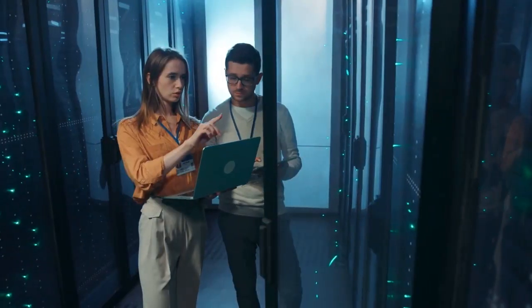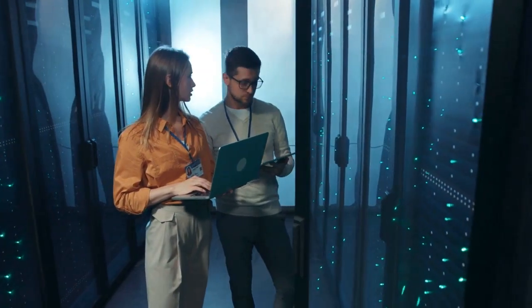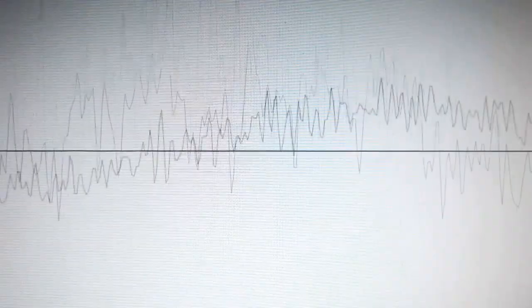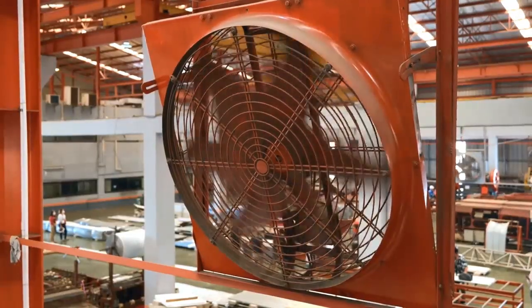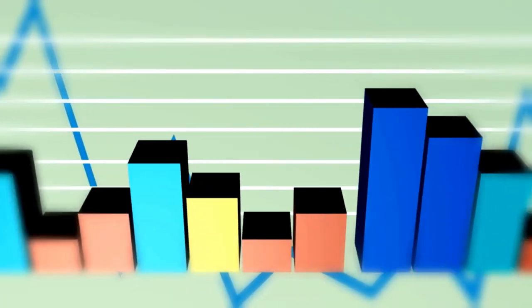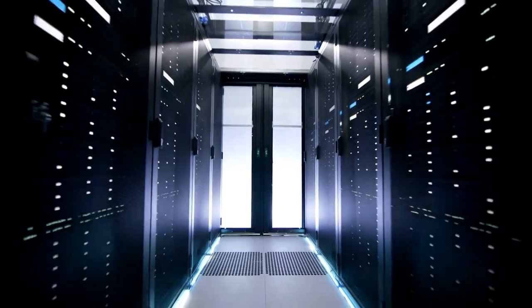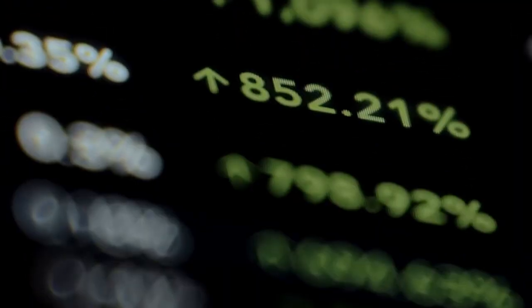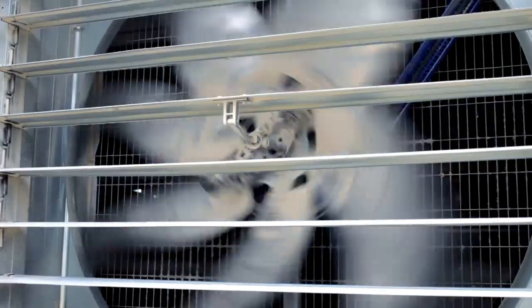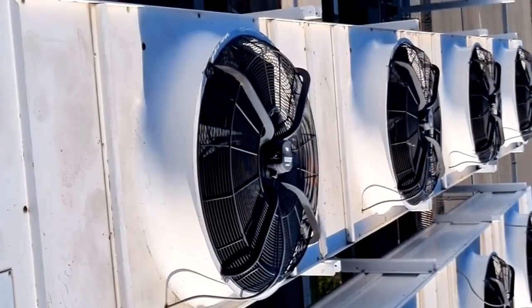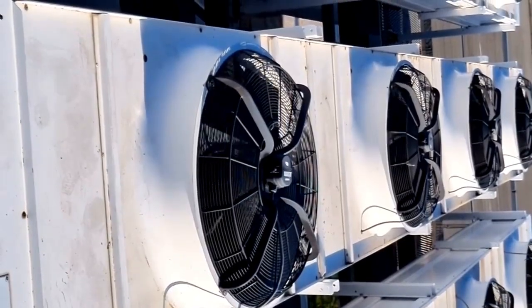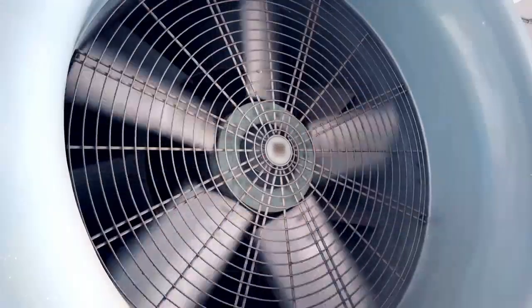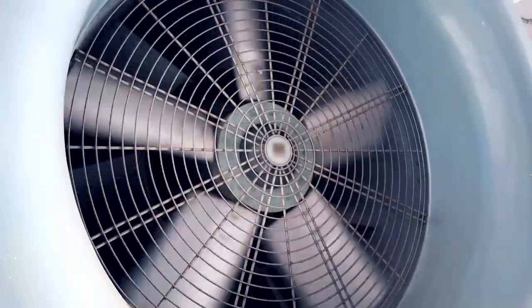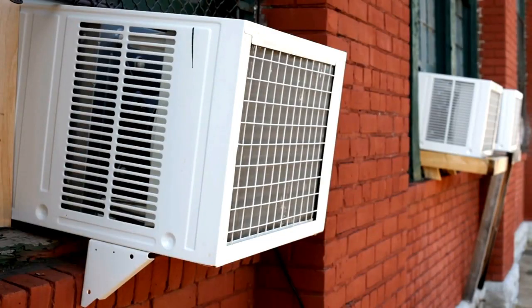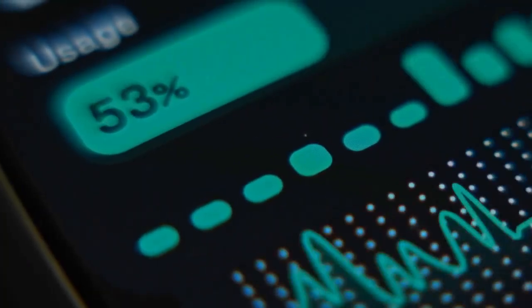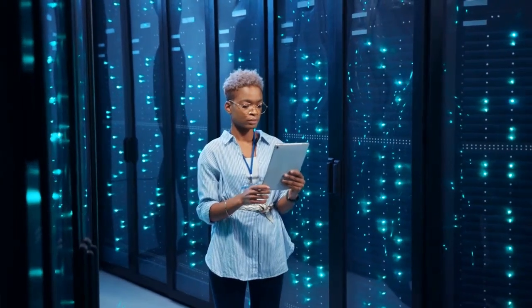Furthermore, the electrical energy required to spin the fans at these absurd velocities creates a self-defeating, vicious cycle. The fundamental heat removal equation dictates that as density increases, the required airflow scales linearly, but the power required to drive those fans scales with the cube of the fan speed. Therefore, a mere 10% increase in airflow demands a massive 33% increase in fan power consumption. Eventually, the cooling fans themselves consume so much electricity, and ironically generate so much of their own mechanical heat, that the cooling system defeats its own purpose, dragging the data center's power usage effectiveness into highly inefficient territory.